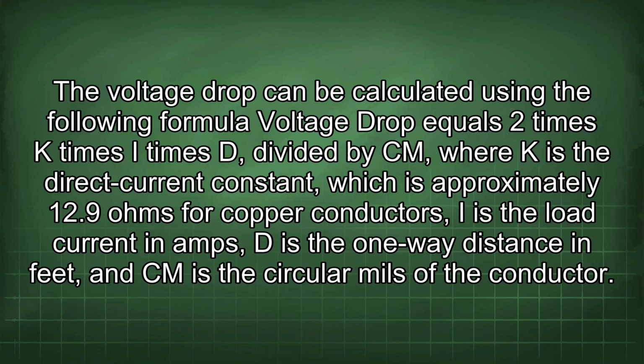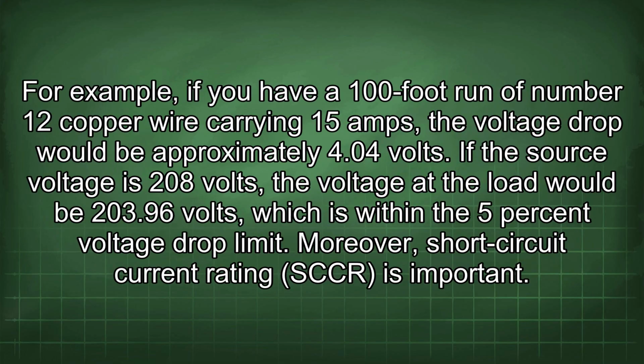D divided by Cm, where K is the direct current constant, which is approximately 12.9 ohms for copper conductors, I is the load current in amps, D is the one-way distance in feet, and Cm is the circular mils of the conductor. For example, if you have a 100-foot run of number 12 copper wire carrying 15 amps, the voltage drop would be approximately 4.04 volts.